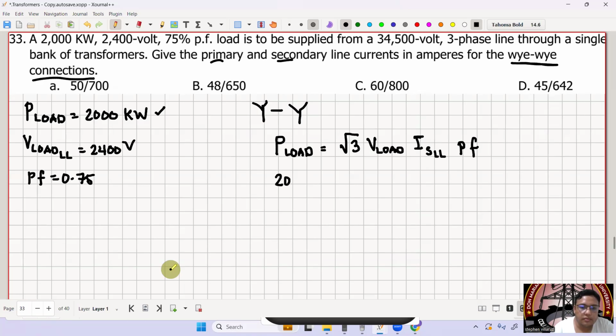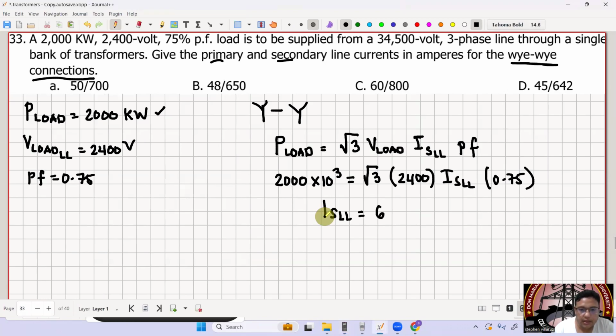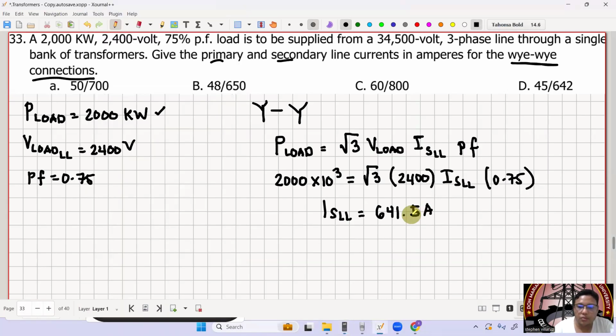So that is now 2,000 kilo is equal to square root of 3 multiplied by your V load. That is 2,400 times your IS line to line multiplied by 0.75. So that is now 2,000 times 10 raised to 3 over square root of 3 ng 2,400 times 0.75. So therefore, this is 641. So IS line to line is 641.5 amperes.